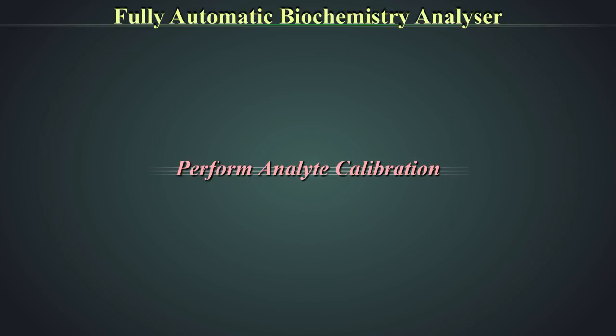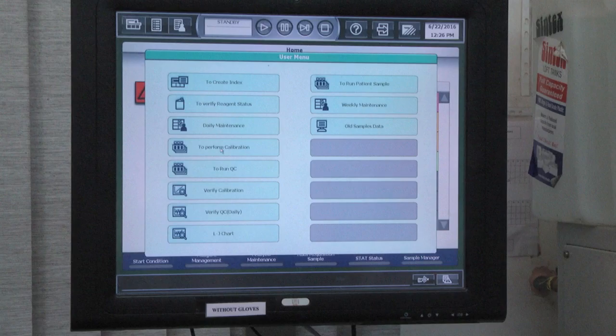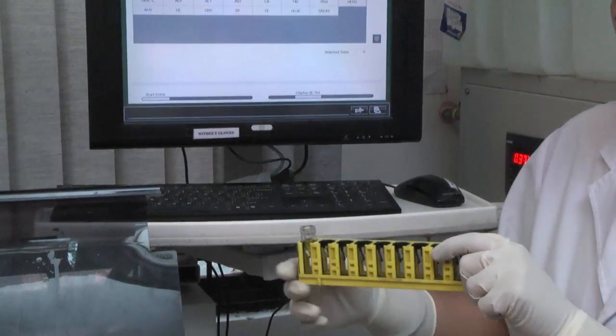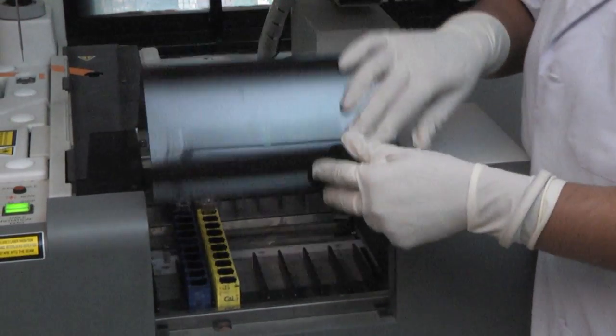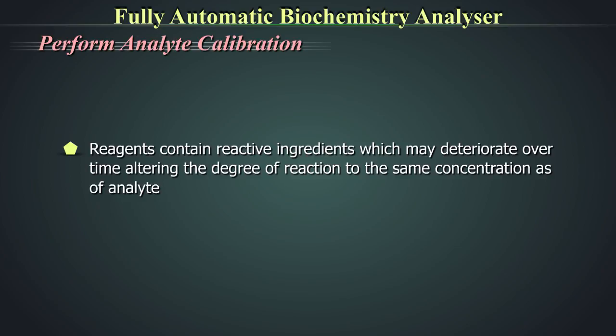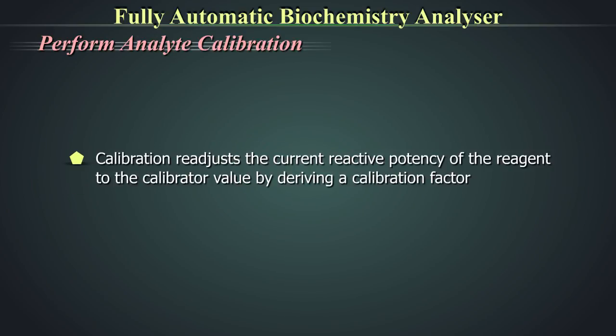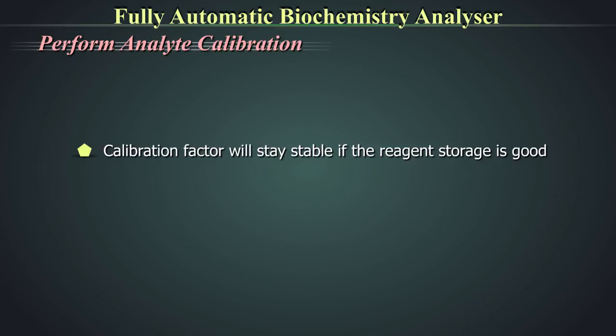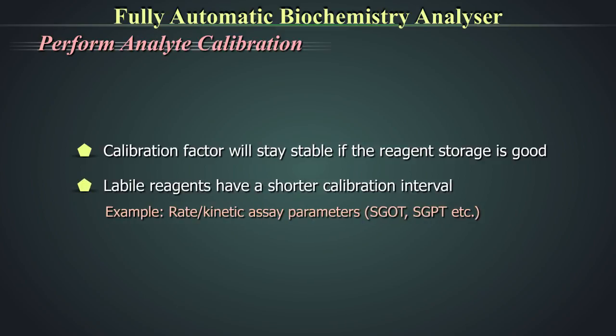During a reagent check, the system automatically orders reagent blank and calibration check for all parameters. Calibrate the analytes requiring calibration. Calibrators are materials with known values traceable to the SI unit through an unbroken chain of comparisons. Reagents contain reactive ingredients that may deteriorate over time, altering the degree of reaction to the same concentration of analyte. A calibration readjusts the current reactive potency of the reagent to the calibrator value by deriving a calibration factor. If reagent storage is good, the calibration factor will remain stable till the expiry of the reagent. Based on the stability of reagents, the manufacturer will recommend a separate schedule for each analyte; labile reagents have a shorter calibration interval.